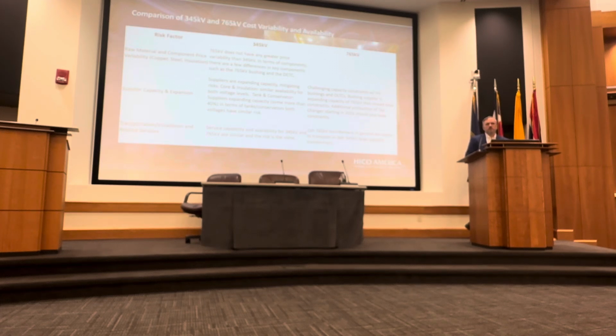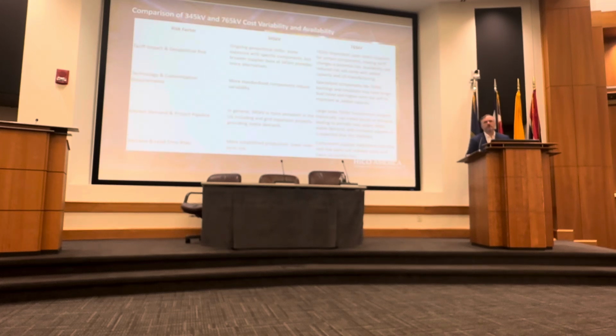One of the things that really gave them a lot of oxygen, though, was where they were going to get this equipment, where they were going to access the breakers, where they were going to access the transformers. When you look at 765, there are very few transformer manufacturers capable of it on a global basis. And as such, the demand for things like bushings is pretty constrained. The average lead time for a bushing on a 765 kV transformer is over 2 years.